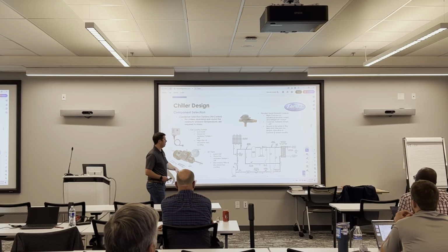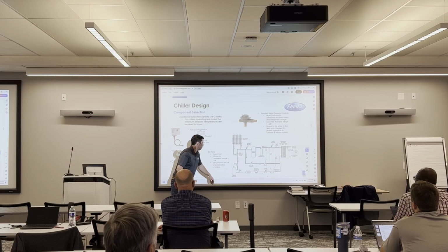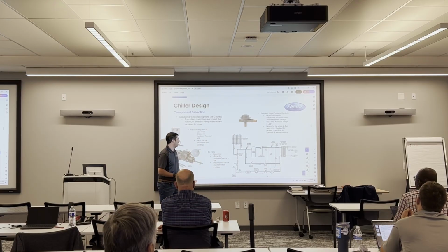So out of our receiver port, it goes into our receiver. Essentially what we're doing here is maintaining the desired pressure on this line. And if we can get pressure here, we're going to stack up pressure through the condenser, and we're going to get a decent head pressure right here.